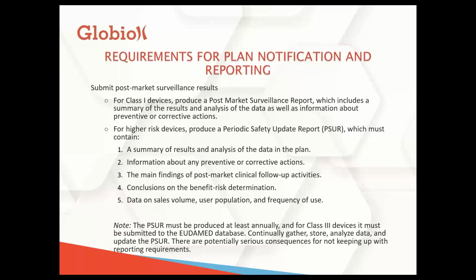And then finally, this is something that is not required by the post-market surveillance report for the lower risk devices, but for the higher risk devices, you want to know how big the problem is, how big the base of customers is. So you need data on your sales volumes, your user population, and the frequency of use of this device. The note down here is just what we said. The PSUR must be produced at least annually, and for class 3 devices, it must be submitted to the EUDAMED database. You are going to continually gather, store, analyze, and report data, and there are potentially serious consequences for not keeping up with these reporting requirements in the new system.